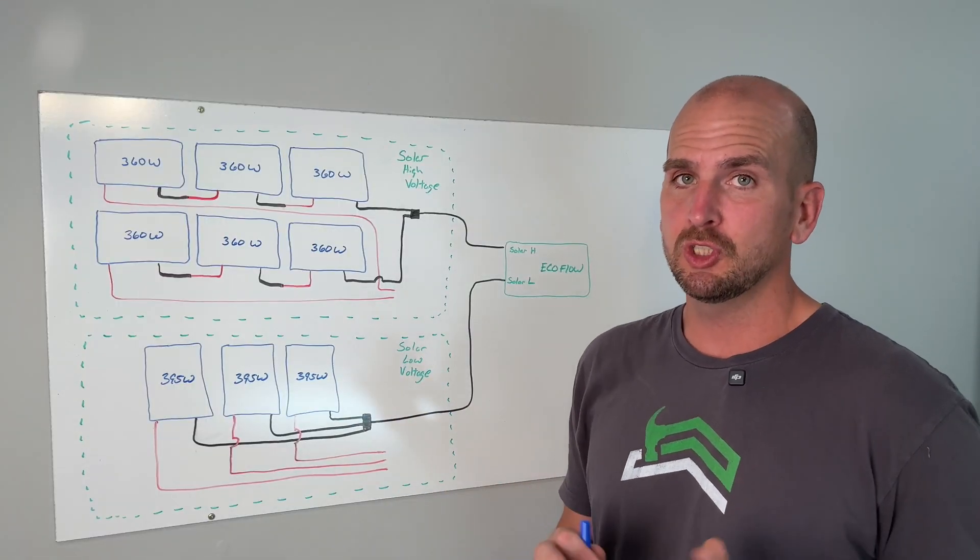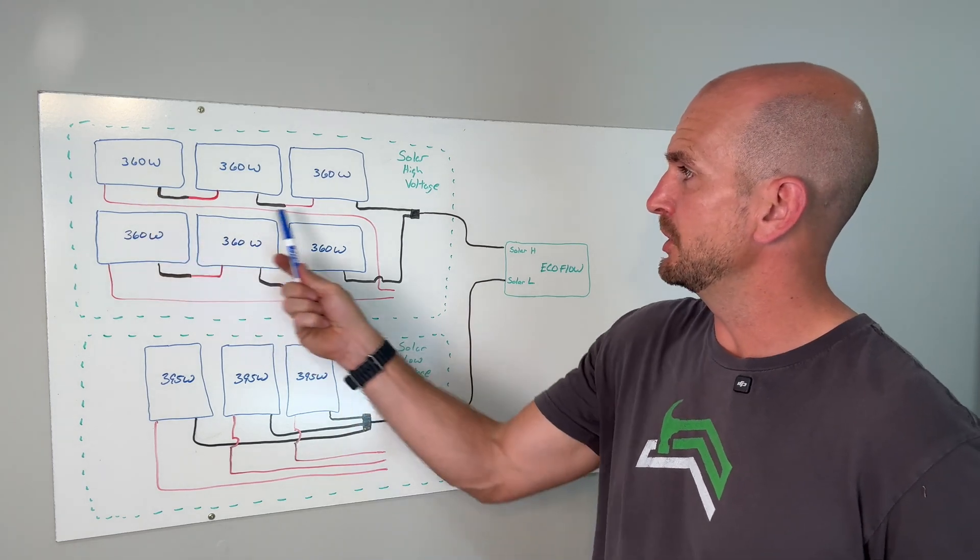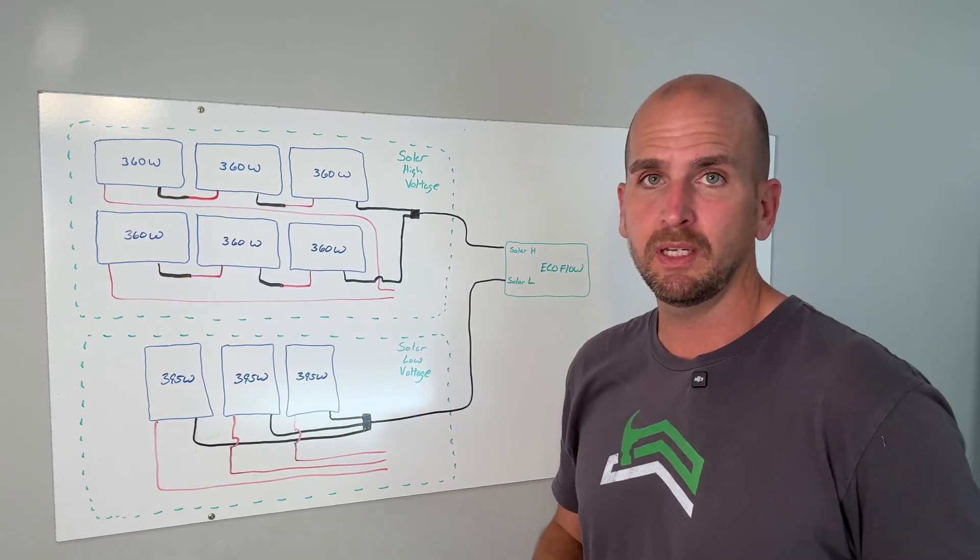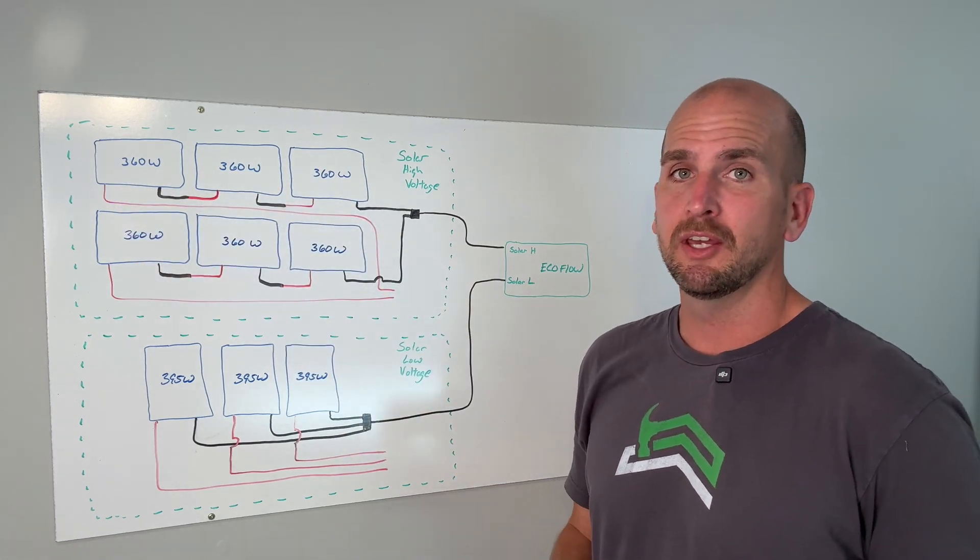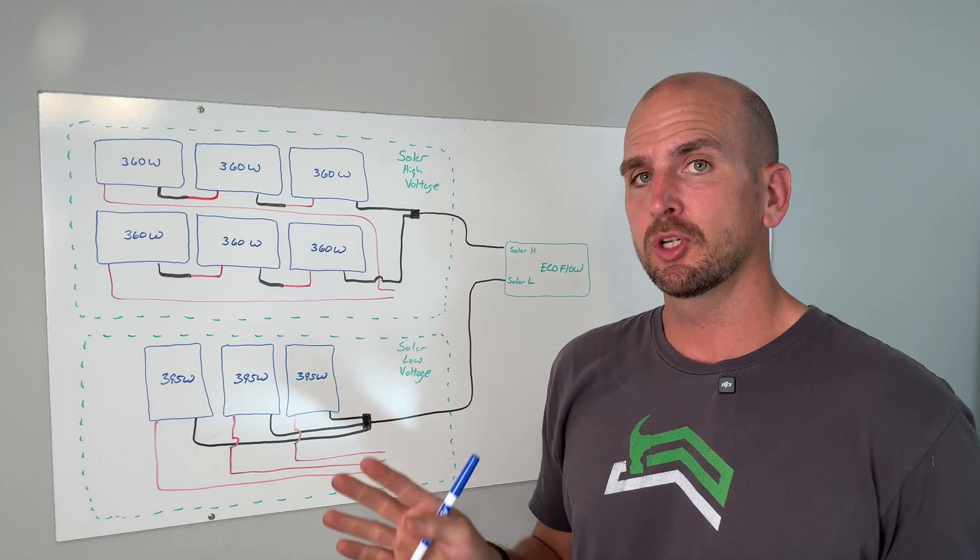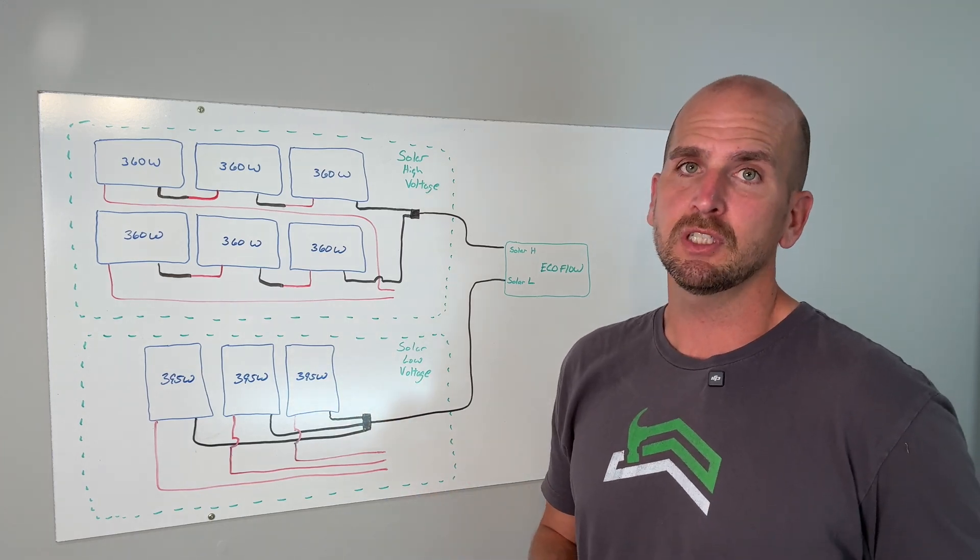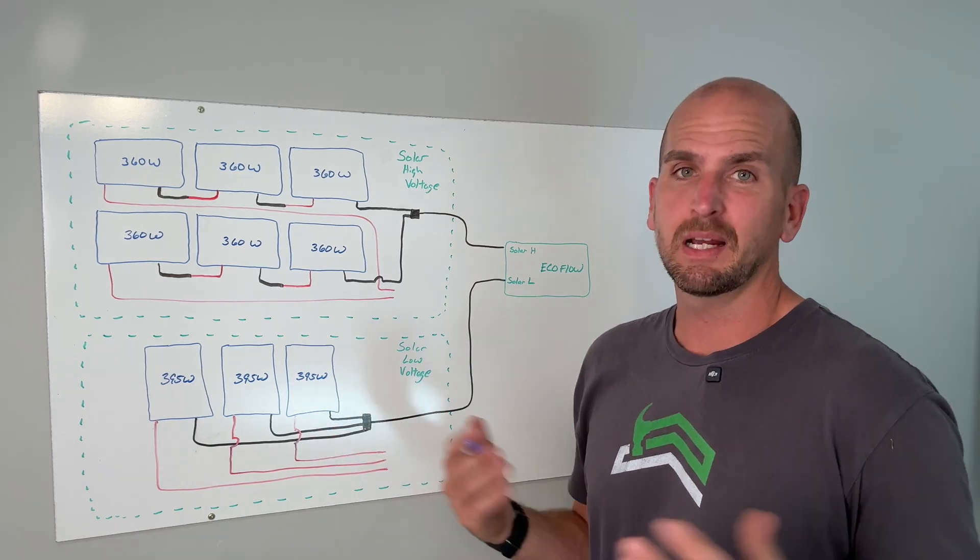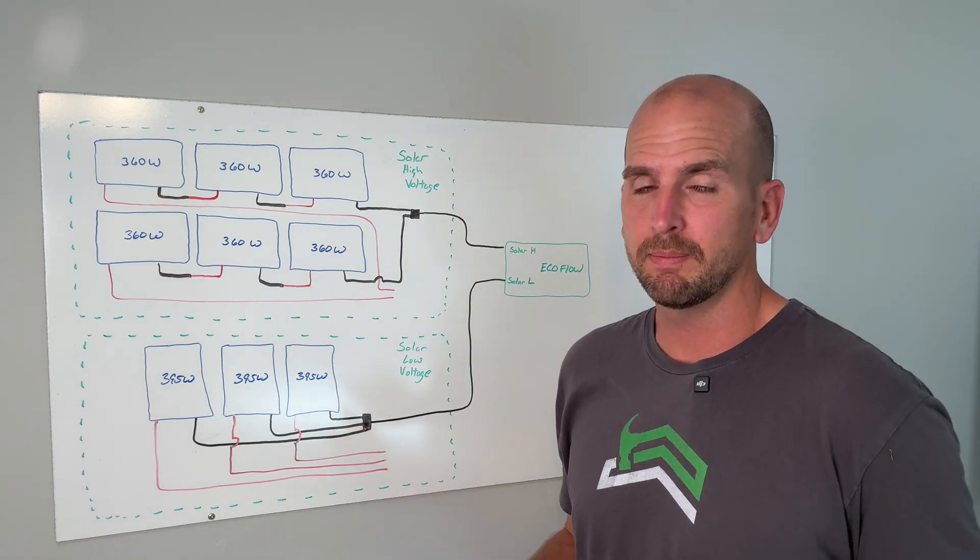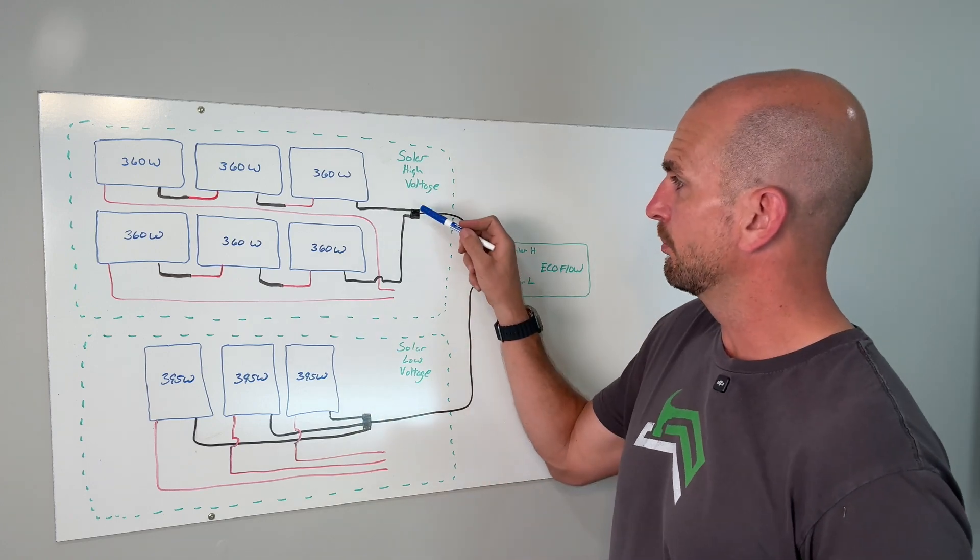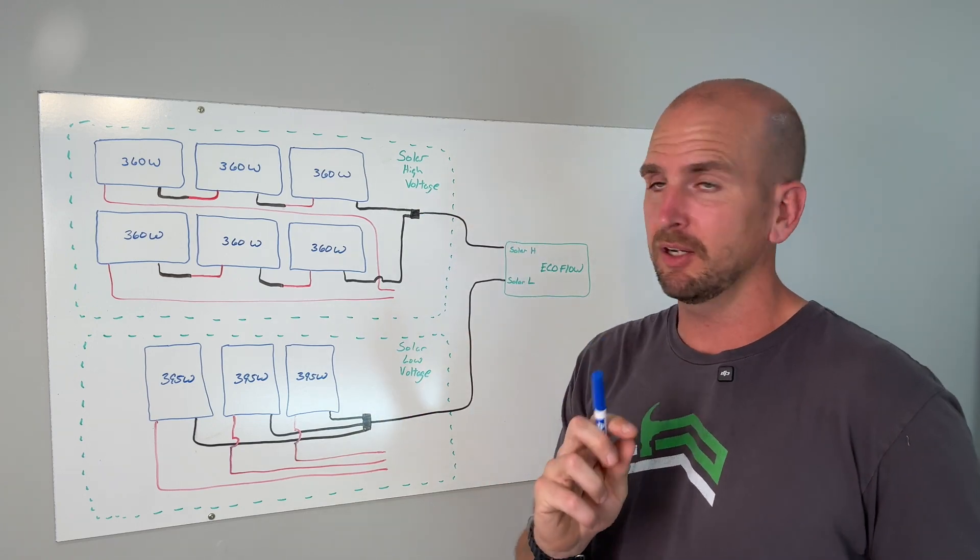Right away if you just have a simple setup maybe just this string of three panels and they're all wired in series you're good to go. You do not need inline fuses. It's when we start to bring things together in parallel.